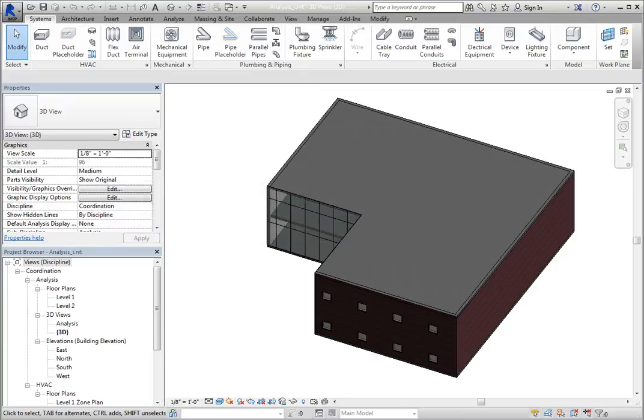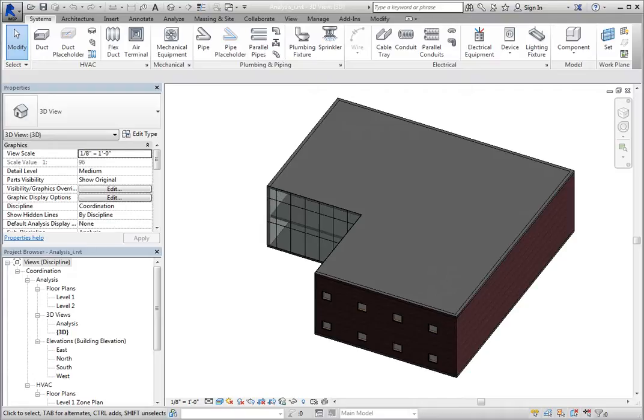The best time to export a GBXML file is early in the design stage, when the model contains only basic building geometry and spaces. Once additional elements, such as furniture and casework are added, the file becomes larger and external programs have difficulty distinguishing all the data in the file.